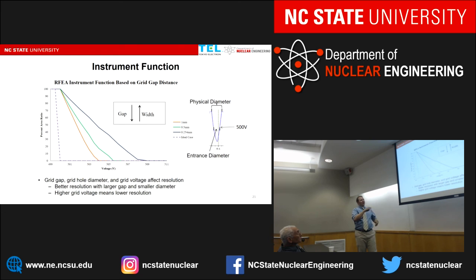And as you can see, as the gap decreases, the width of this instrument function gets larger, meaning that our resolution is getting worse, because it's not going to be as sharp a transition with the 500 eV ions, which should measure as just a peak at 500. Instead, with this larger one, it's going to be a peak maybe closer to 504, which means we're now 4 volts off instead of, for the example of the orange, 2 volts off.